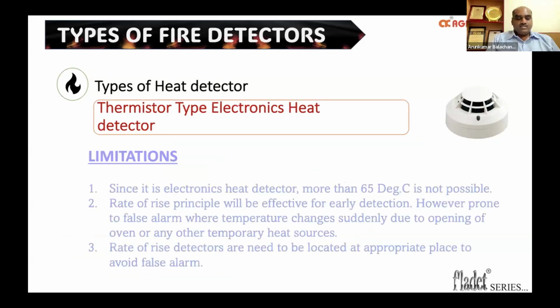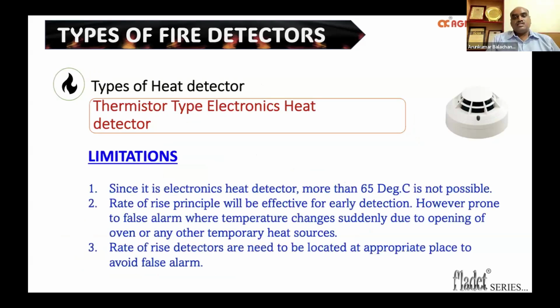The limitation of this detector is that, since it's an electronic type, we cannot use these detectors in ambient temperatures of more than 60 or 65 degrees centigrade. And also the rate of rise, though in principle it is a point of early detection, is also prone to false alarms.